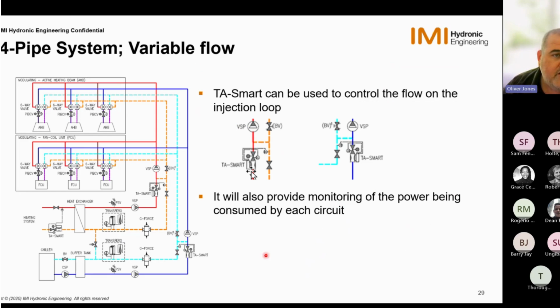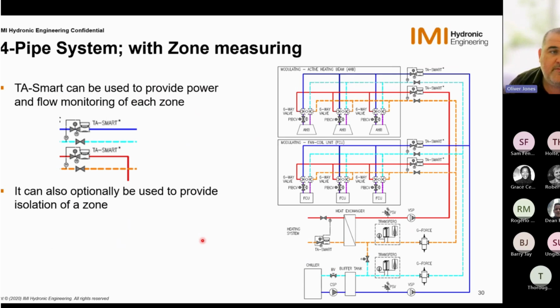On a 4-pipe system, so variable flow, the Smart can be used to control the flow on our injection loops, and it will also provide monitoring of the power which is being consumed by each unit, and that data, as I say, is available within the cloud, and you can extract that to see or to offer up to your client if need be. 4-pipe systems with zone measuring, so we can use it to provide flow and power monitoring of each zone where they are placed typically on here. So we've still got standard PICVs on the AHUs and fan coils, but on each zone, instead of having commissioning sets or anything like that, or a heat meter, we basically use the TA Smart instead of isolation, heat meters and flow measurement devices, and we can provide all of the flow monitoring and power monitoring and also isolation of the zone itself.